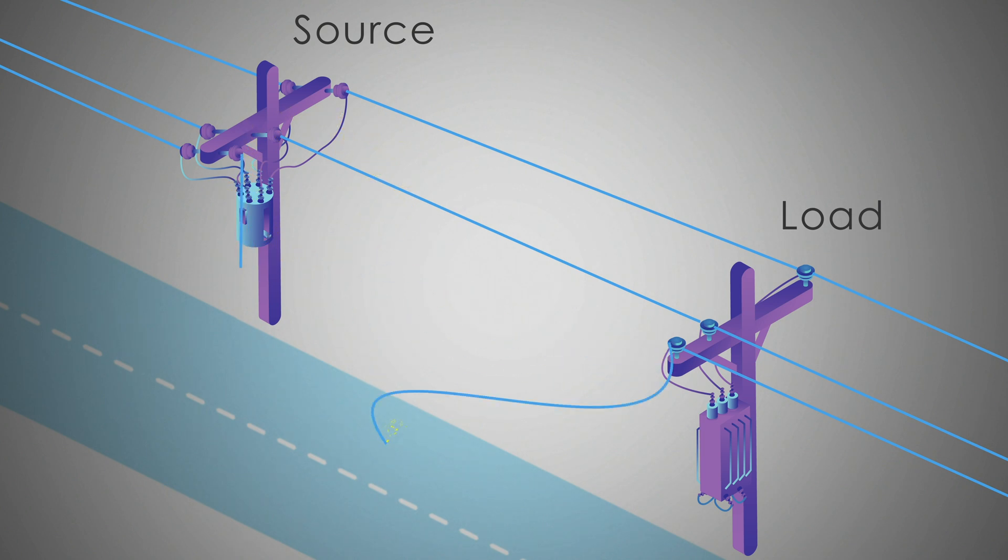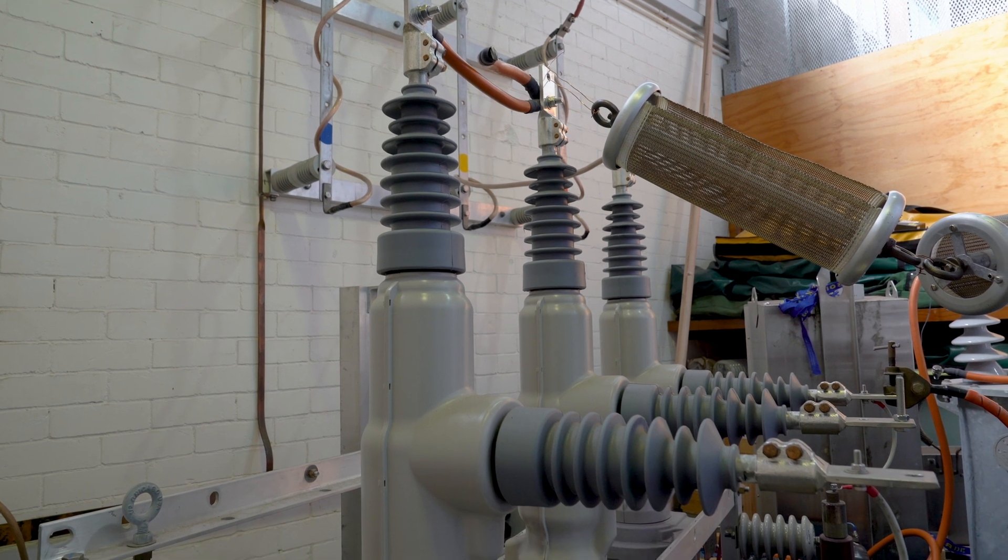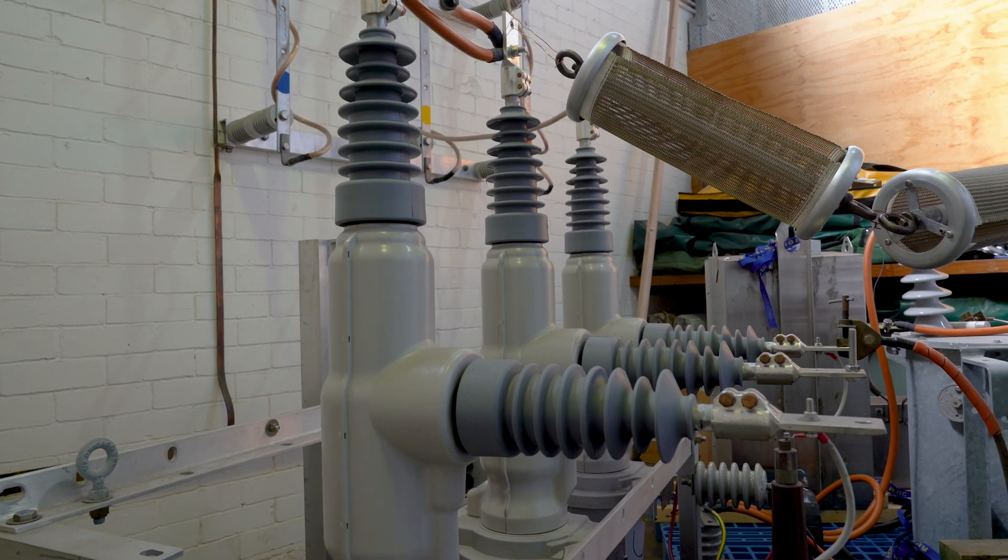But if the conductor falls on the load side, only a very small current of perhaps as little as 100 to 200 milliamps of earth fault current will flow. That's far too small for any high voltage protection system to accurately detect.